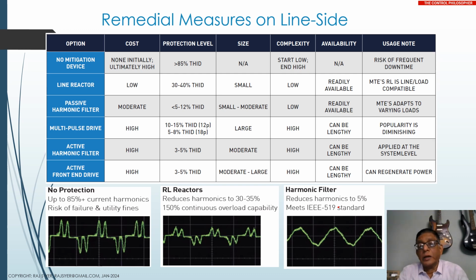What is an active front end? This active front end interacts with the line itself. This is what manages the feeding back of active and reactive power into the supply line. So active front ends are commonly found in regenerative drives. This table lists out the different methods and the cost and things. But yes, these days the modern drives which are available are capable of inherently having a low level of harmonics.